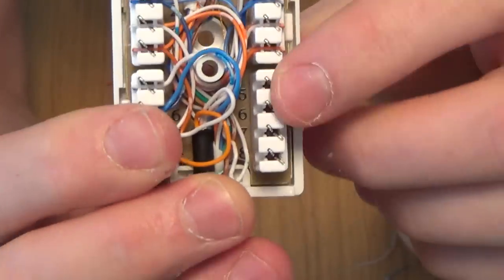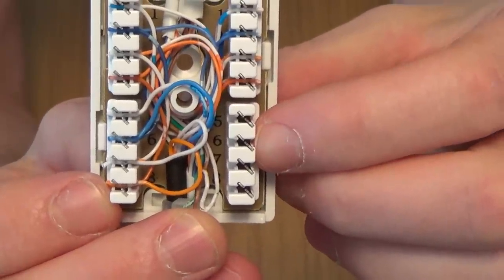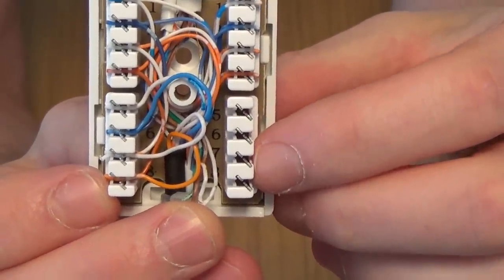And now we have these terminals here free for fitting two more cables. So you can put the white-blue to number five, the blue to number six, the white-orange to number seven, and the orange to number eight. And that's how you can connect up to six cables in this little junction box, and it will work absolutely fine.